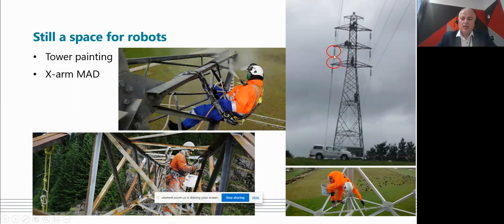So it's from the bottom of the insulator up onto the cross arm, or from the bottom of the insulator and conductor to the cross arm below it. That phase to earth clearance is just a killer, so the minimum approach distance is an issue there. We cannot paint these tips with this circuit live.